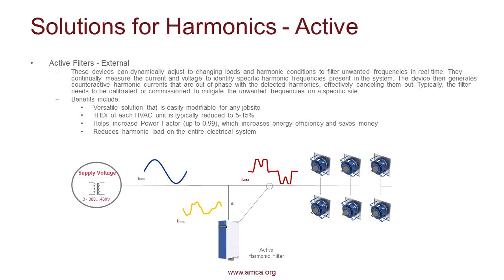Typically, we can see the THDI reduction to 5 to 15%. And here in the active filter, we're actually increasing the power factor close to that 0.99. So this is increasing energy savings and saving you money, increasing efficiency. And it's also reducing your harmonic load on the electrical system.